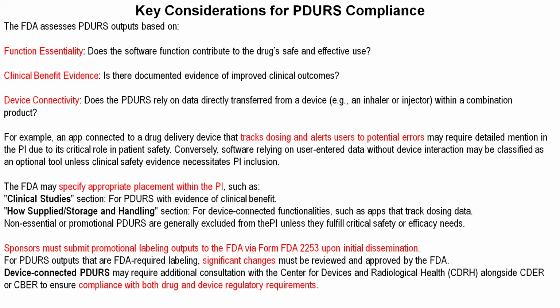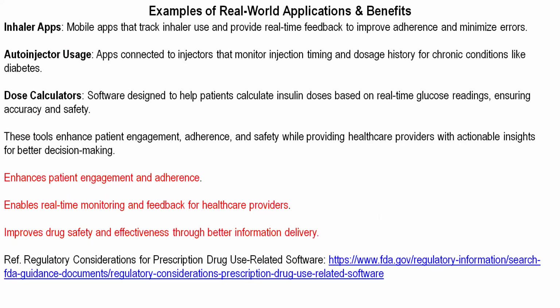So this device falls under different types of FDA scrutiny. You know, there are 510(k) or de novo, whatever, depending on their use and their risk. So there is a double side to the requirement. FDA clearance is required, and in the PI they can specify clinical study or storage and handling, something like that. The example, I think this is the FDA document, is very limited.